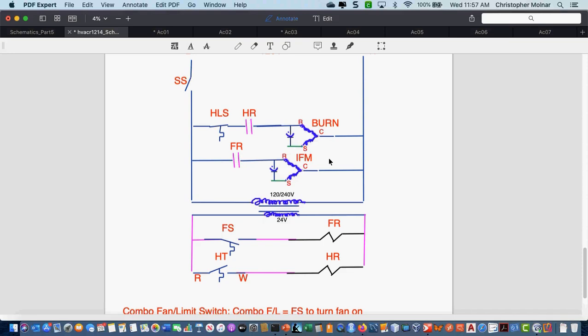Okay, because heat rises. So that burner is going to put off a little bit of heat. That furnace will cool off just because it's sitting there. The burner is going to come back on. Heat the furnace up again to about 200 degrees, shut it back off. So that limit switch will allow that furnace to cycle but not get to a condition where it's going to catch fire. Do I want it running like that forever?